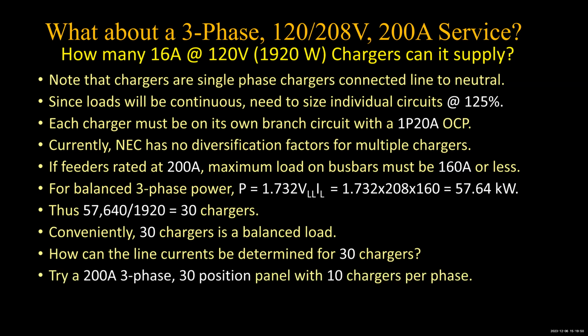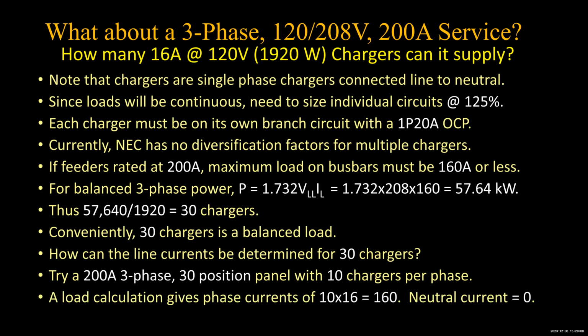Well, the fun of that is that, let's say you got a 200 amp 30 position panel, because that's going to handle 30, 20 amp, one pole circuit breakers. And we put 10 chargers on a phase. All right, load calculation, phase currents says we got 16 amps on each of 10 circuits. That's 160 amps, no neutral current. So that's what we're supposed to have, 160 amps per phase.